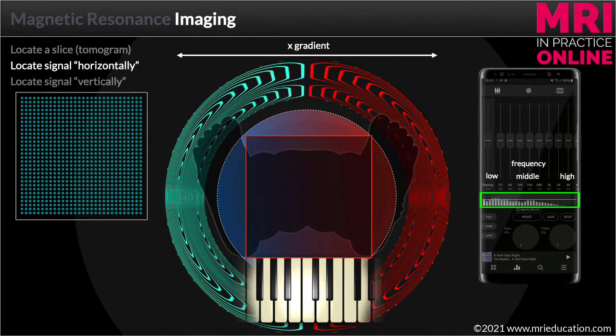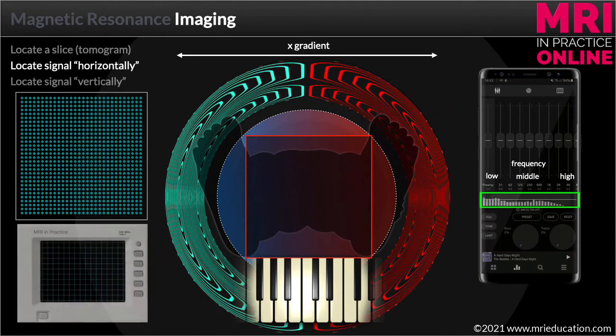Importantly, the amplitude of each sample point is not the same as the amplitude of the signal returning from the apparently equivalent pixel on the image. When we collect the signal it's a waveform, and with the gradient switched on it will contain a whole range of frequencies. If we look at a row of data points and plot their amplitude over time on an oscilloscope, it's a rather more complex waveform, because the amplitude of each sample point is a combination of all of the different frequencies returning from the patient at that moment in time. If the scanner can identify these frequencies, it can assign them a spatial location along the axis of the gradient. Let's perform a spectrum analysis like the one on my phone.